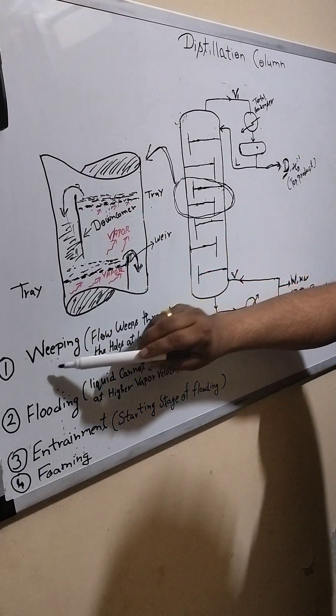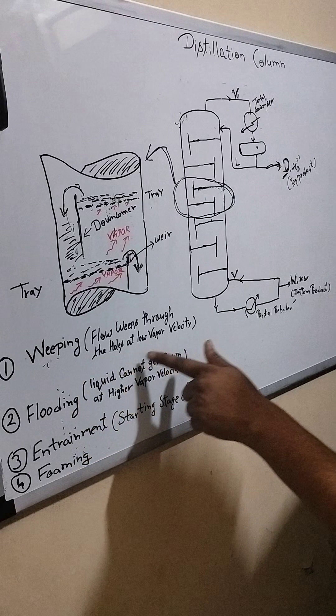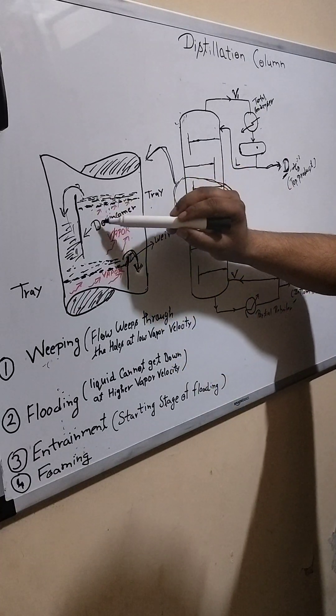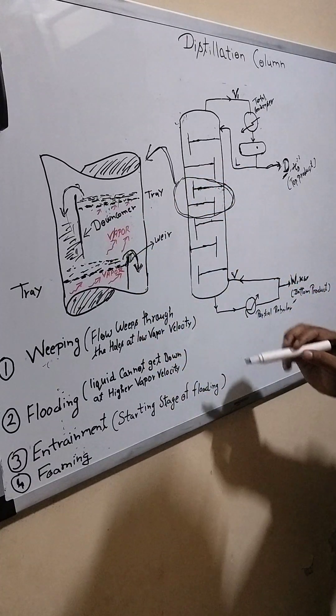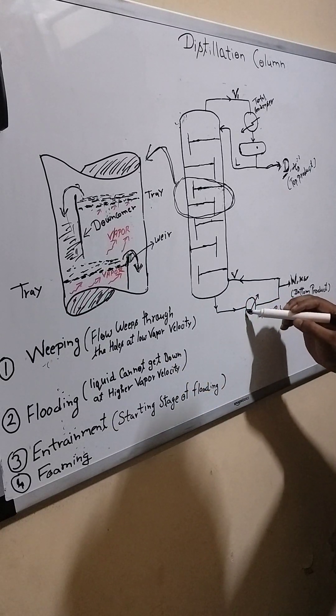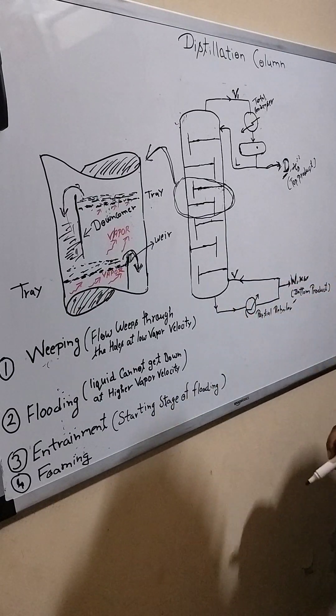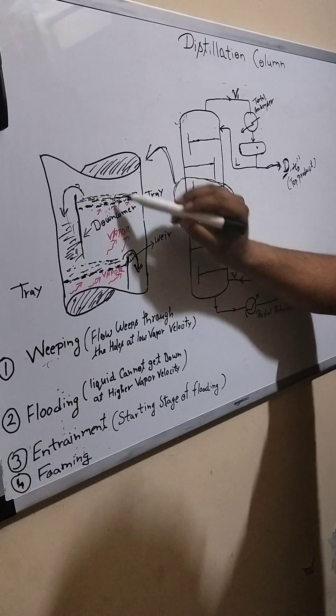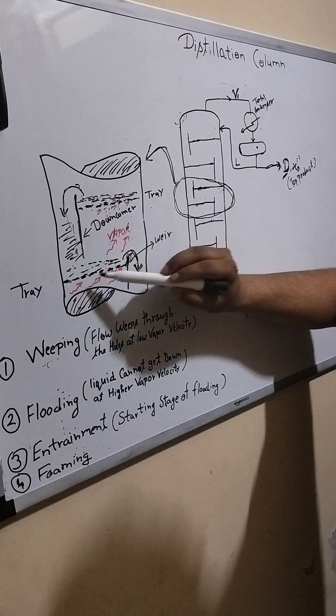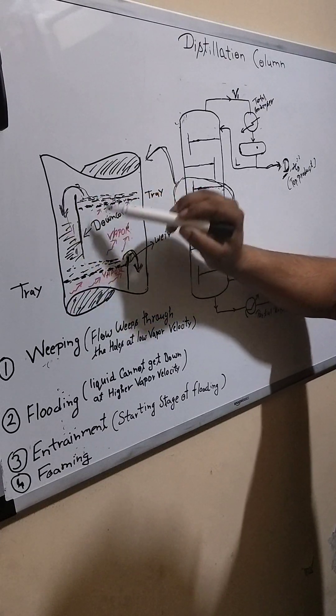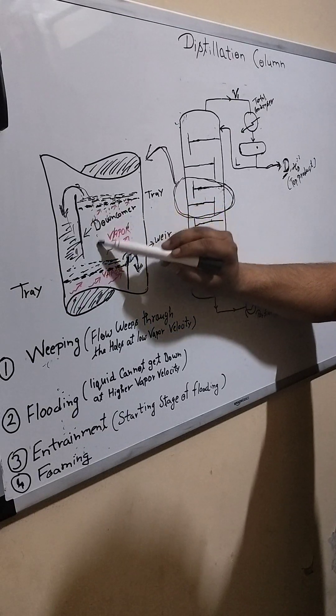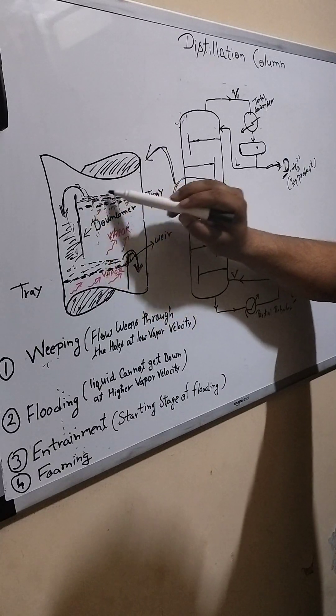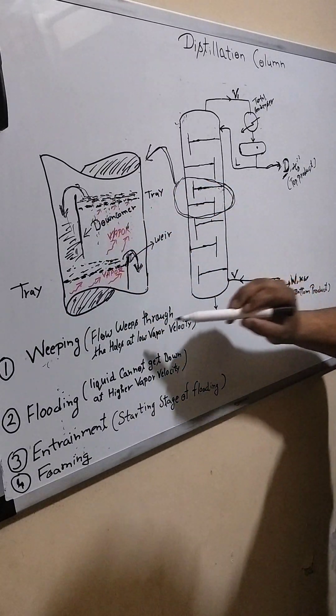When weeping occurs, the reason of weeping is: in weeping, what happens? Liquid weeps through the holes at low vapor velocity. Due to the low vapor velocity, suppose your steam is not sufficient to vaporize the certain amount of vapor, so vapor velocity will reduce, and liquid will just fall down from these holes. It will not come across this downcomer. It will just fall like rain through these holes. Why does it happen? It happens due to low vapor velocity.